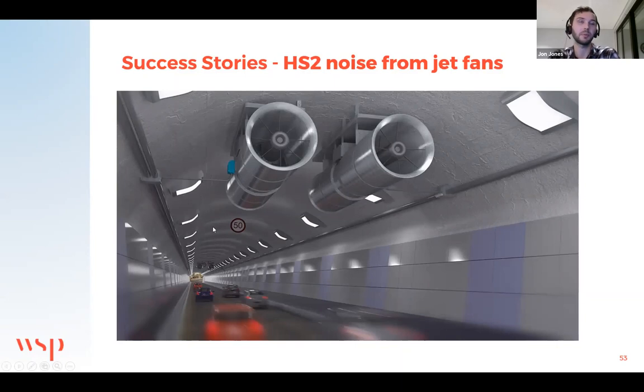However, we were able to interrogate that a bit further, and through understanding the extent of the exceedance in criteria, both in terms of increased level, but also the extent in terms of the plant area on the platforms that was affected, we were able to agree a relaxation and actually agree that these fans were acceptable, because the principal requirements, the drivers for the acoustic criteria, which was predominantly the intelligibility of the public address and voice alarm systems, were not impaired.